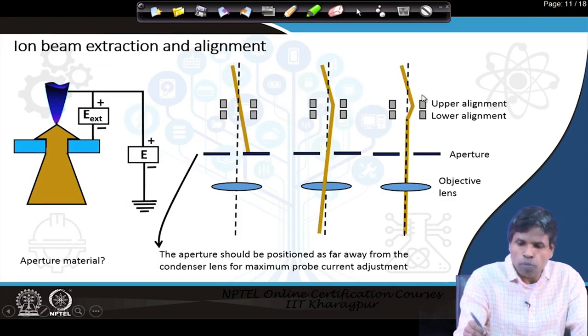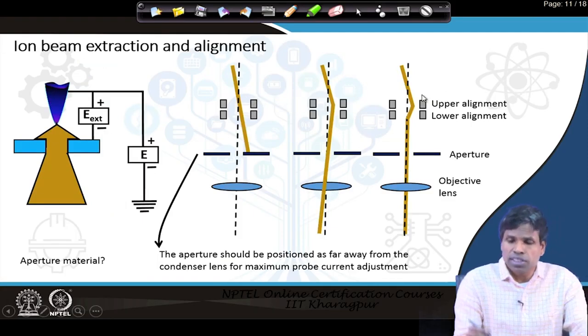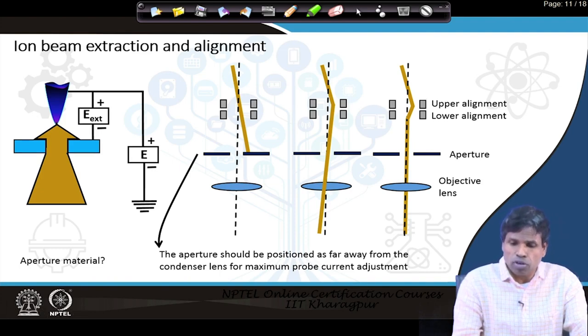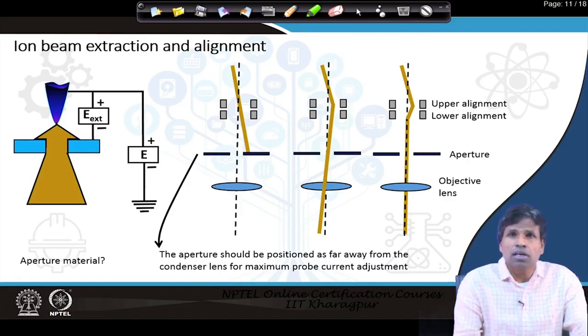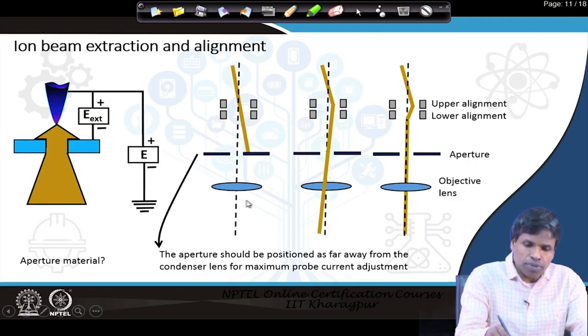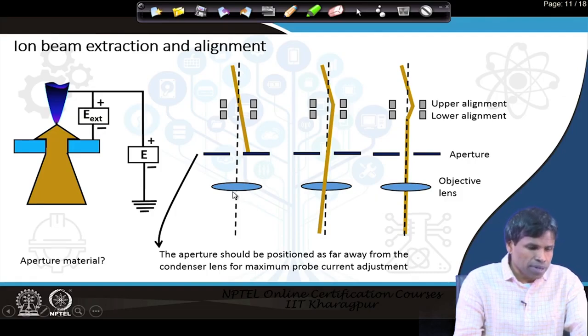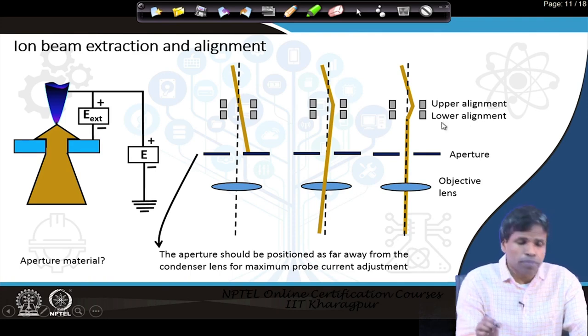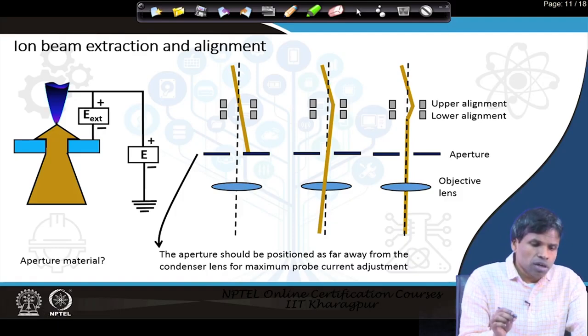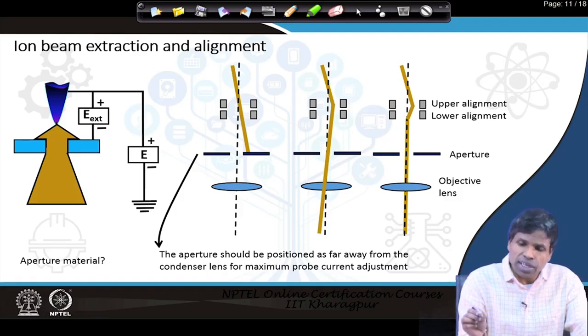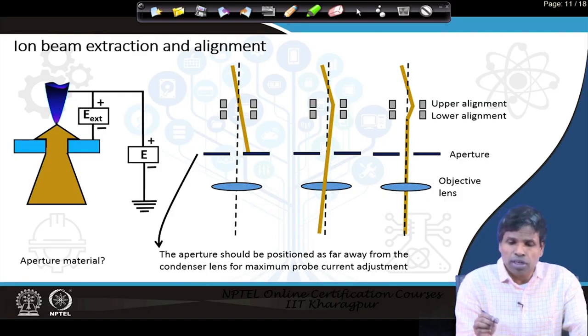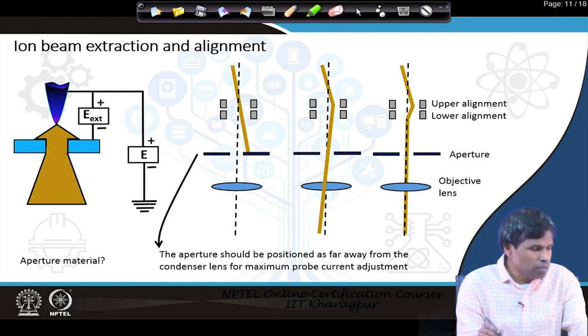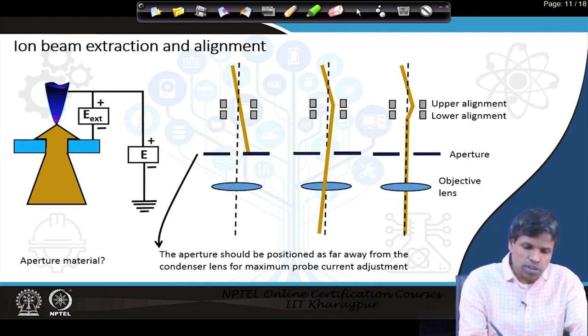There is upper alignment and lower alignment — this is the first electrostatic alignment process. By applying suitable voltage, we could align the ion beam through the optical axis towards the objective lens. This upper and lower alignment each have a set of components — one for x-direction alignment and one for y-direction alignment — and a suitable potential is applied so that the beam is directed downwards along the optical axis.